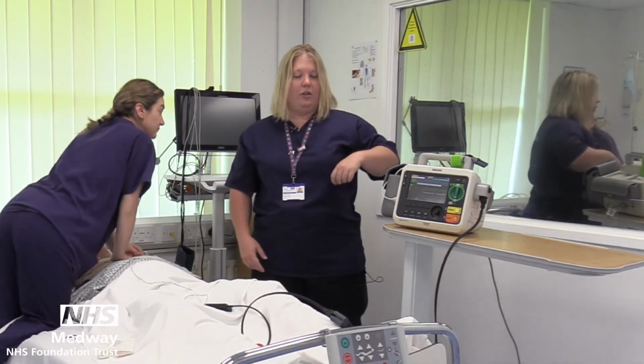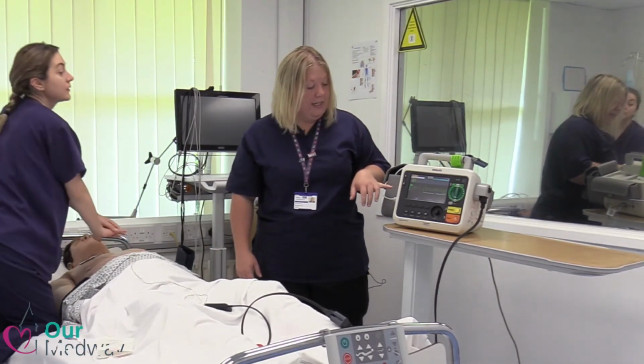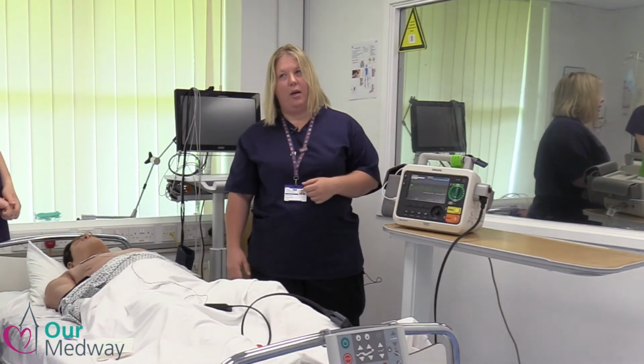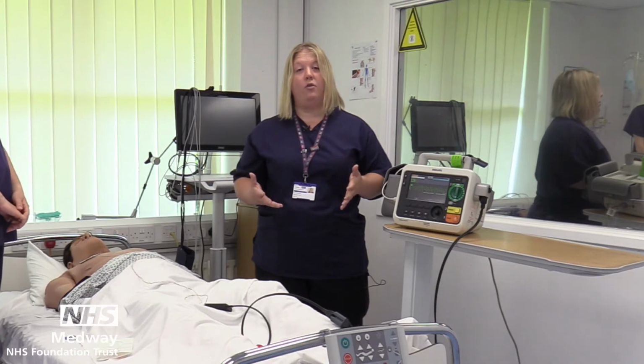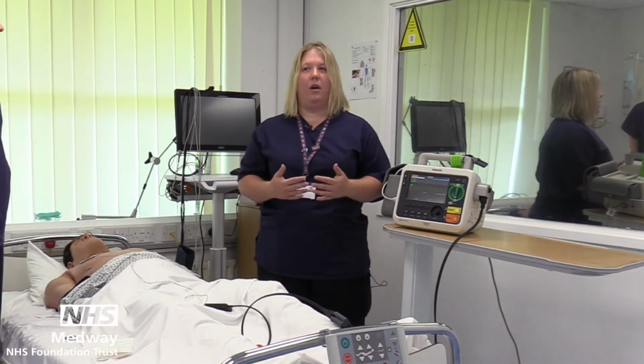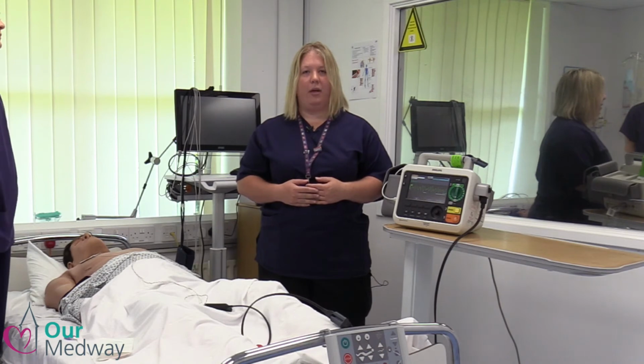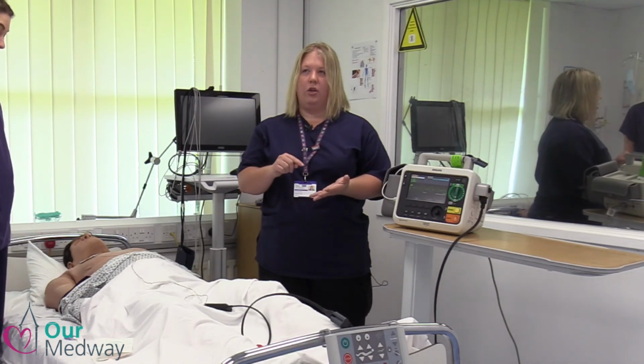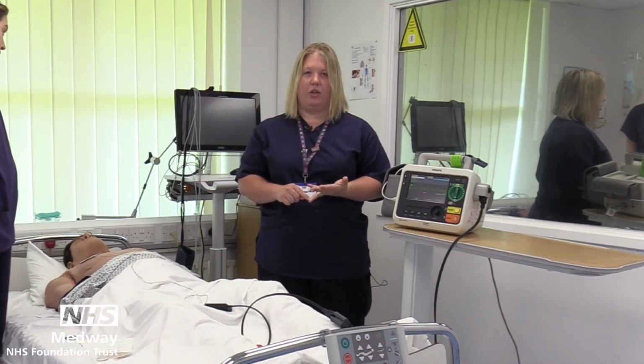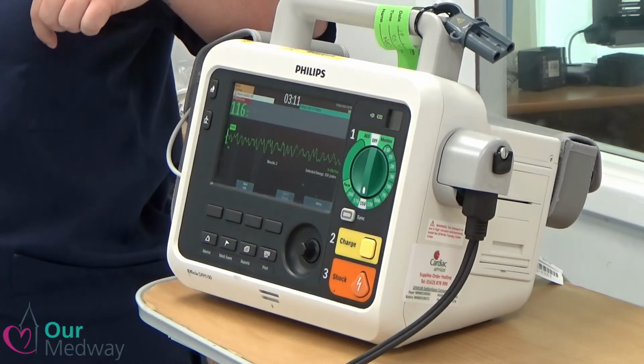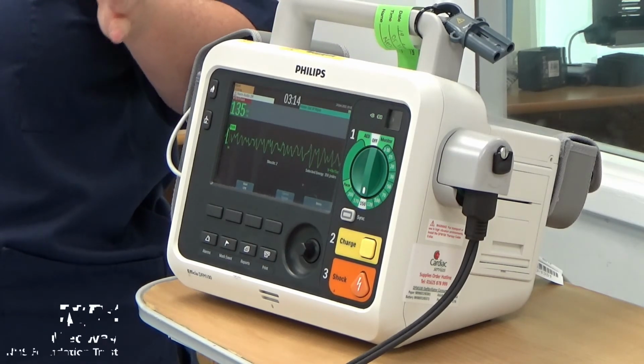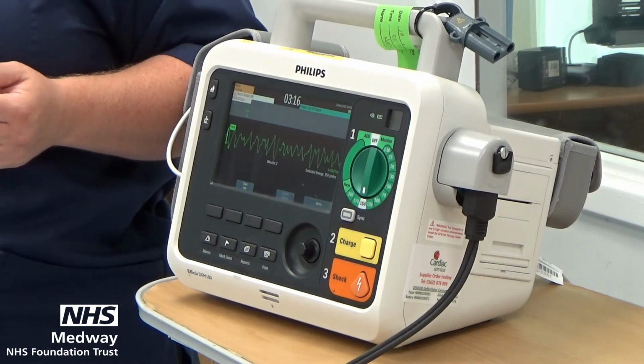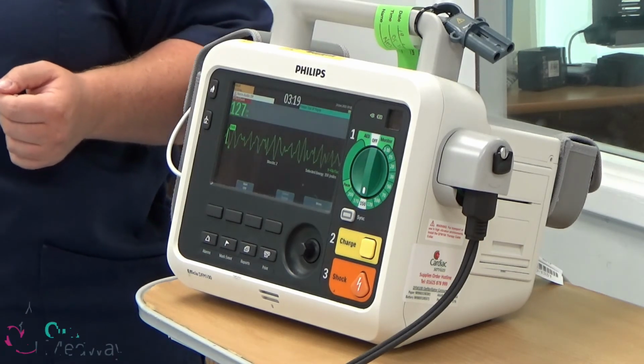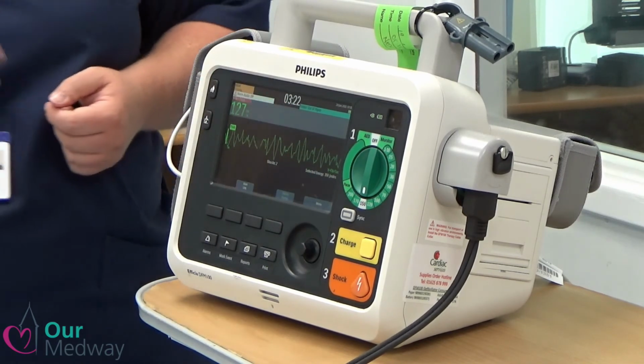Begin CPR. And you again will notice that unlike AED mode, there is no 2-minute timer that comes across on the screen. So in manual mode, it's very much down to the team. It's very much down to the person operating the defib, like I say, to know the rhythms, to know the energy that needs to be charged, and to keep the time. There is a timer at the top of the screen. This is a continuous timer from the moment you turn your defib on to the moment you turn it off. So at the point you deliver the shock, you note the time, and then every 2 minutes from there, we would pause for a rhythm check.